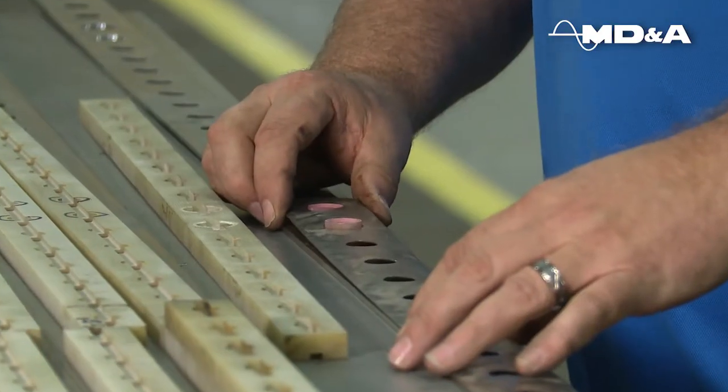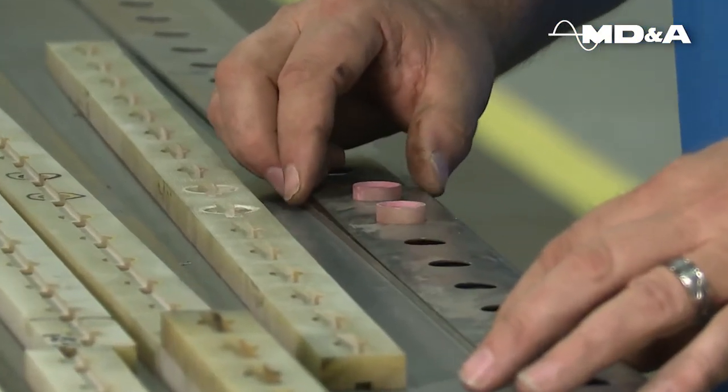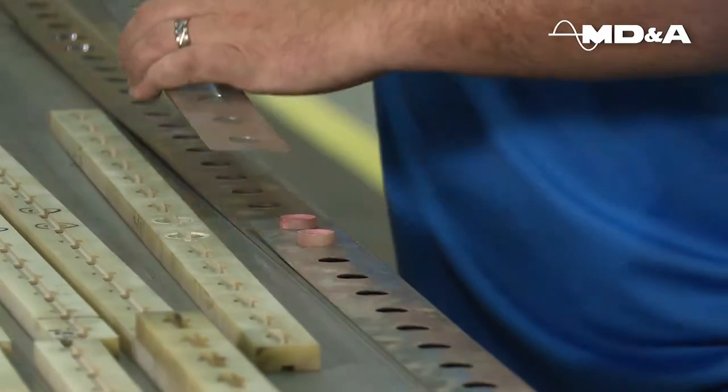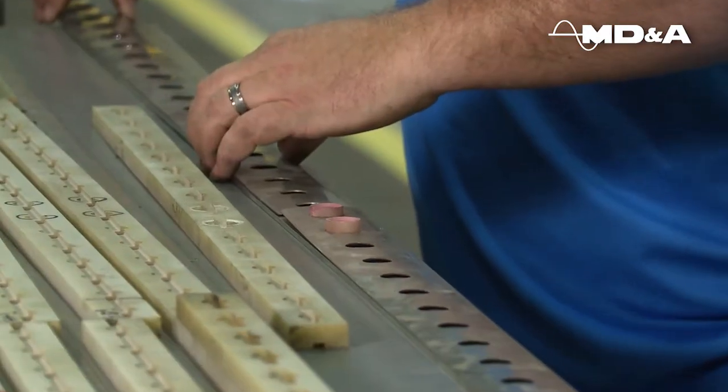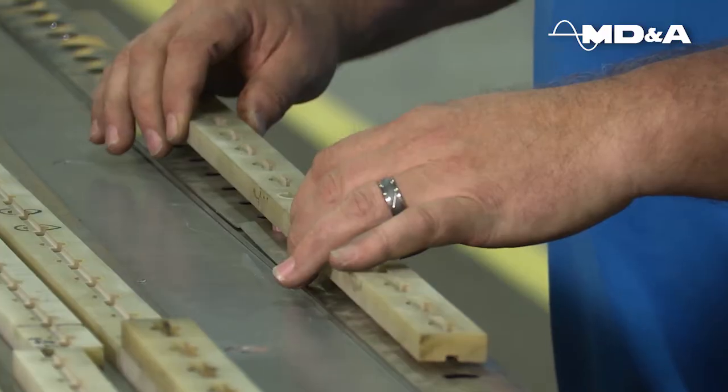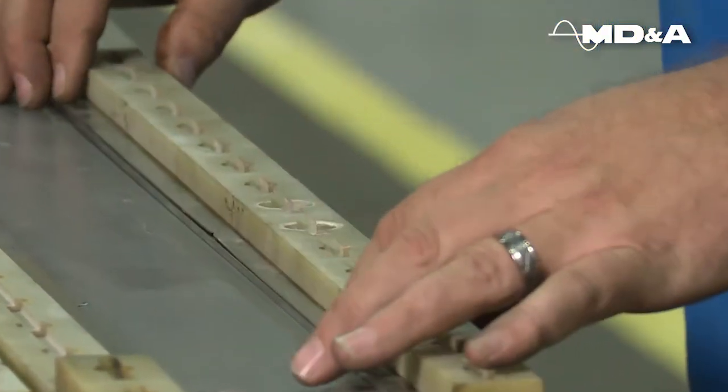MD&A's repair adds two top hats in each spring. Made of a G11 glass, these pieces fit in the modified holes to stop the springs from migrating axially. This prevents them from blocking the vents.